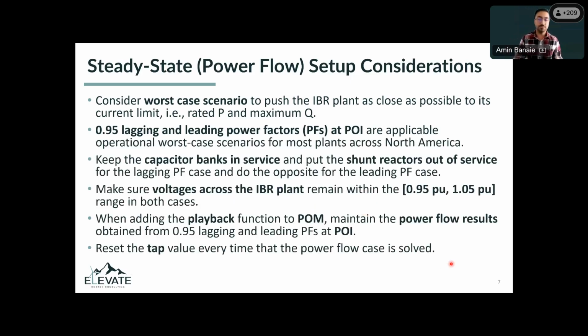And then once we have done these checks and we have good confidence in our model, the second step is to set up our power flow case. For this, we consider the worst case scenarios. The reason for that is to push the IBR as close as possible to its current limit, and we want to evaluate the IBR ride-through performance around that worst case scenario. That would be rated active power and maximum reactive power generation.